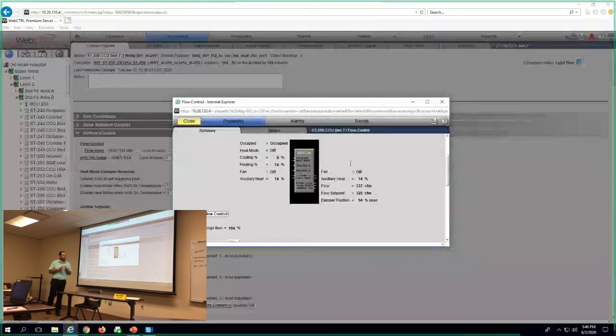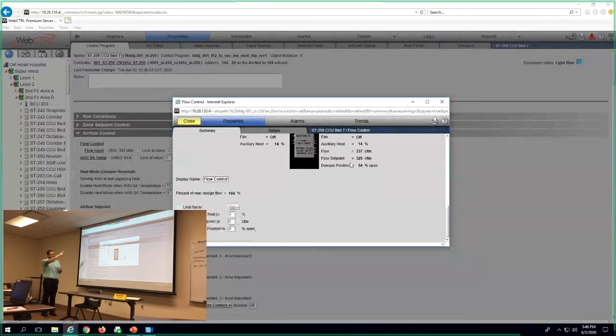From right here, we're going to talk a little bit about troubleshooting. If you arrow down a little bit, Joe, you see down here, this VAV doesn't have a fan, so you don't have to worry about that. This is just a can on every one of them, but this is not a fan-powered VAV. You can lock that flow set point to a particular number if you want to. So make it 400 and hit accept.